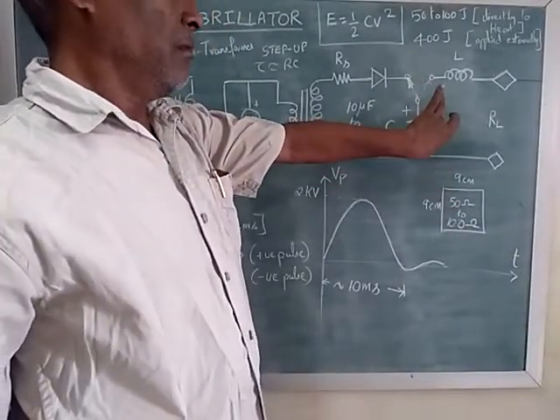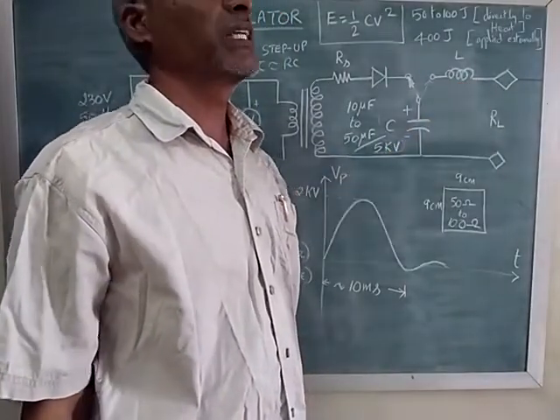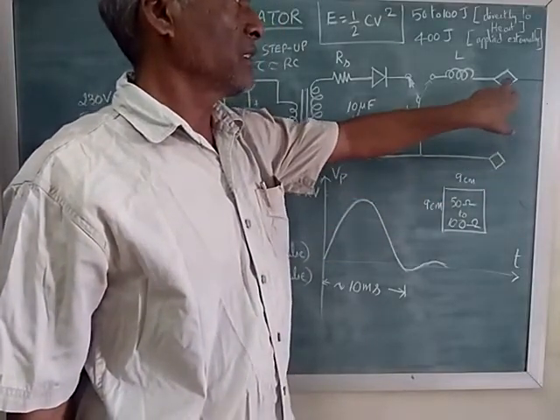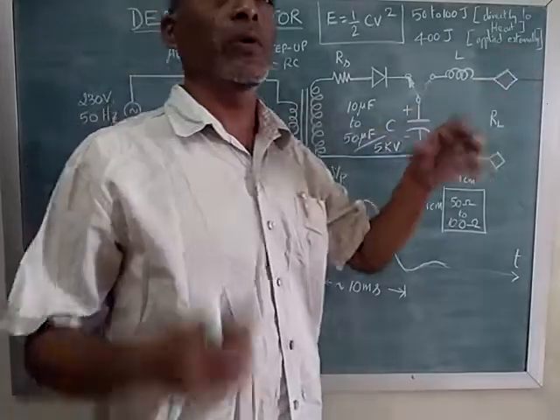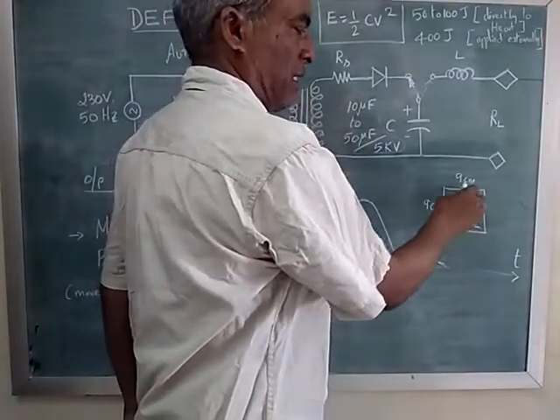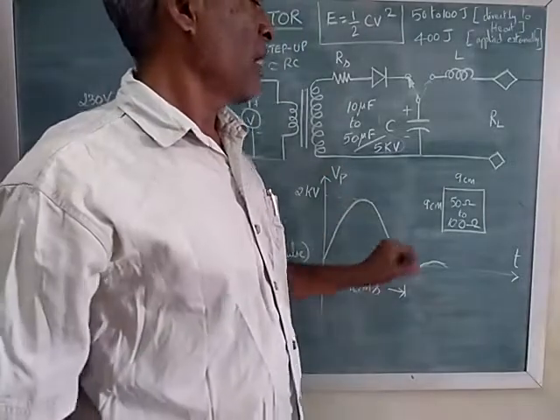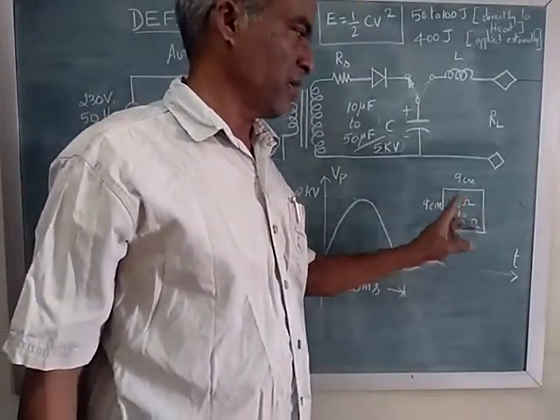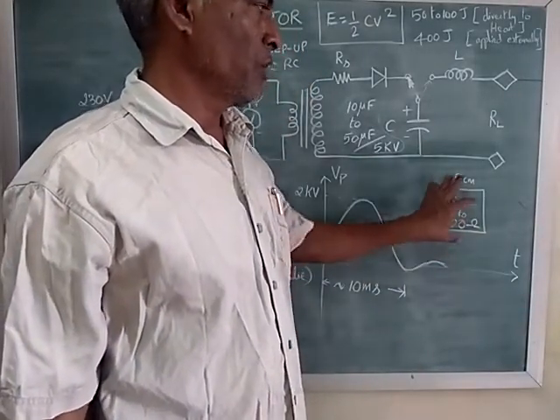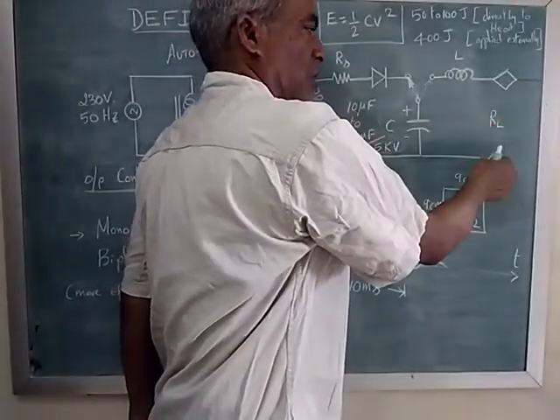So the voltage here starts discharging through this capacitance. L, you all know that L, inductance will oppose any current variations. That's why we have included inductance. And this is one electrode, another electrode. These two electrodes are placed over the chest. The area of the plates is 9 centimeter by 9 centimeter, so roughly nine nines are 81 centimeter square area. And these plates will have a resistance in between 50 ohms to 100 ohms. That depends. So we know the area, that means we have the resistance. So this can be considered as 50 to 100 ohms here also, 50 to 100 ohms.